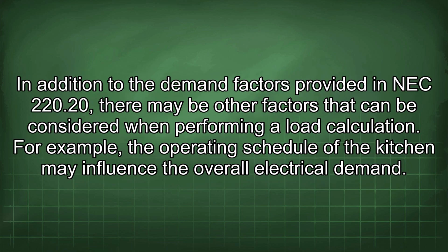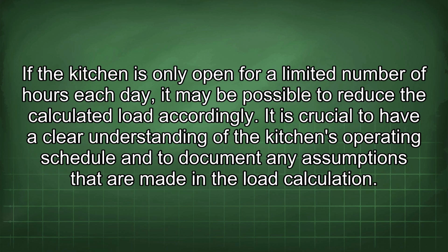In addition to the demand factors provided in NEC 220.20, there may be other factors that can be considered when performing a load calculation. For example, the operating schedule of the kitchen may influence the overall electrical demand. If the kitchen is only open for a limited number of hours each day, it may be possible to reduce the calculated load accordingly. It is crucial to have a clear understanding of the kitchen's operating schedule and to document any assumptions that are made in the load calculation.